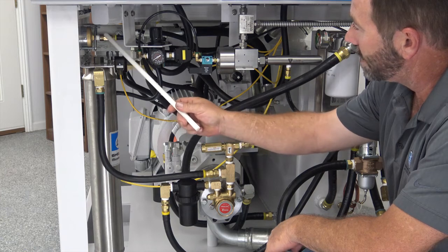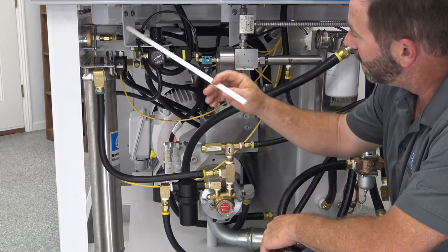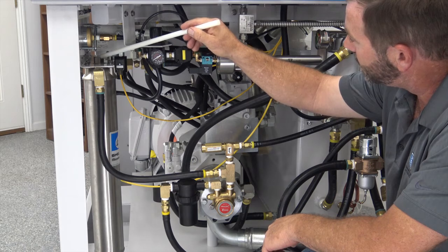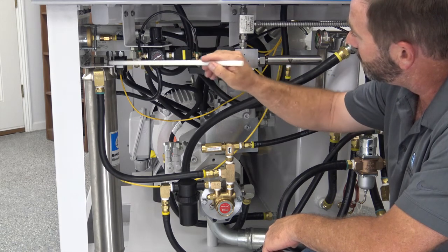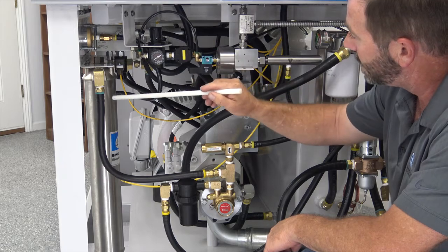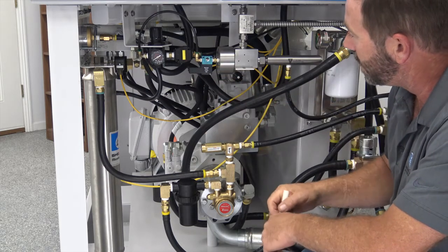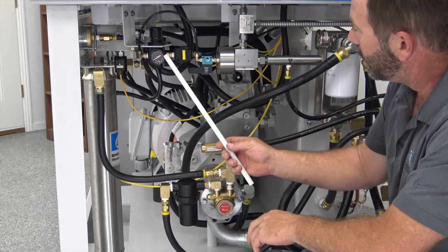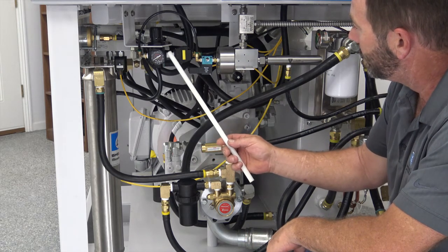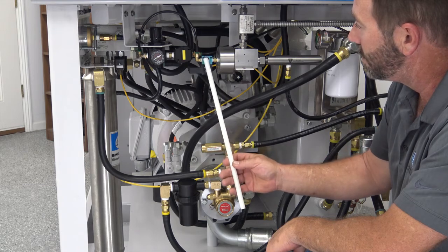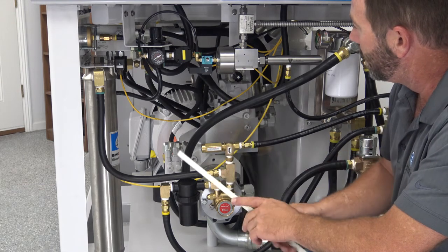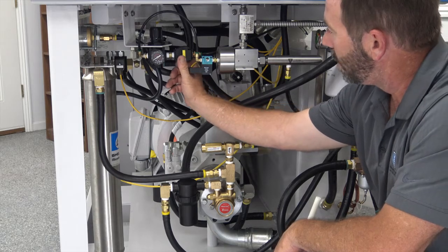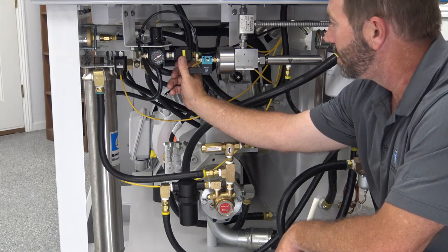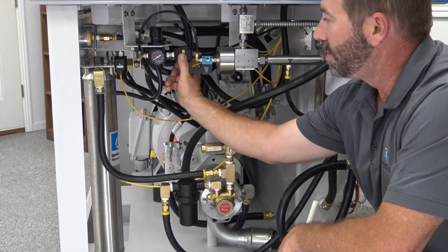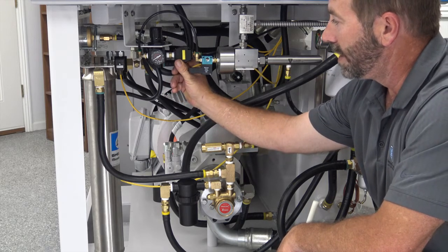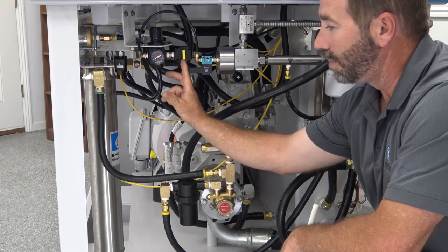You can also see the back side of the gauges and stuff here, the hosing, and this small nut that's on the top of this. When you get ready to change your filter, you turn that counterclockwise and loosen that, and it lets you take the sump off of this filter housing. If we work our way to the right, we have our air pressure regulator. That basically regulates the air pressure going to this normally open valve. As you can see, it's got a small yellow lock on it. If you have a lockout tagout procedure when you're getting ready to perform maintenance, you can simply slide this back and forth, and it allows you to put a lock through that hole that's in the side of it.